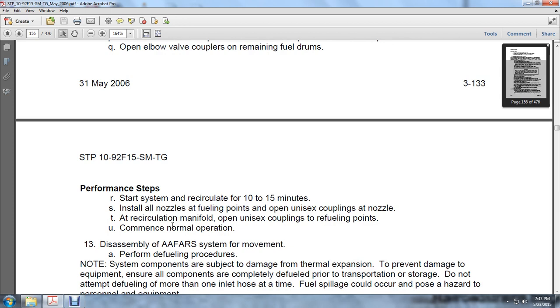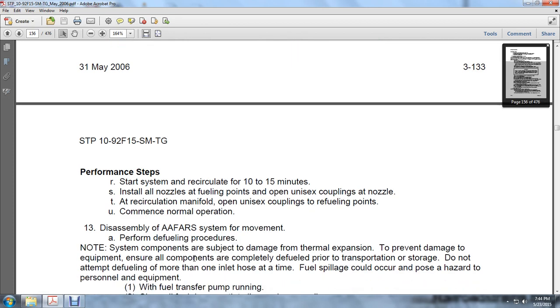Start the system and recirculate for 10 to 15 minutes. Install all nozzles at the refueling points and open the unisex coupling at the nozzle. At the recirculation manifold, open the unisex couplings to the refueling points. Commence normal operation. Okay, disassemble the advanced aviation forward area refueling system for movement.